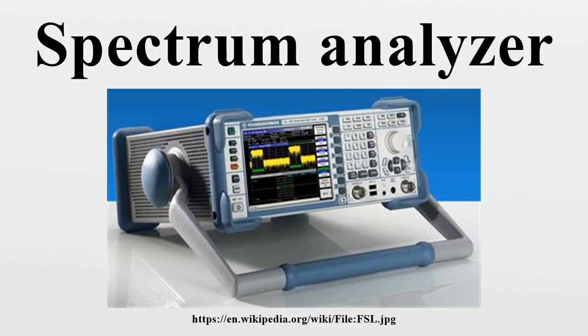Resolution bandwidth. As discussed in the operation section, the resolution bandwidth filter, or RBW filter, is the band pass filter in the IF path. It's the bandwidth of the RF chain before the detector. It determines the RF noise floor and how close two signals can be and still be resolved by the analyzer into two separate peaks. Adjusting the bandwidth of this filter allows for the discrimination of signals with closely spaced frequency components, while also changing the measured noise floor.